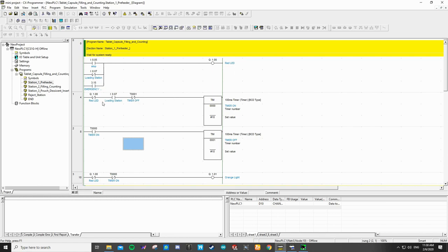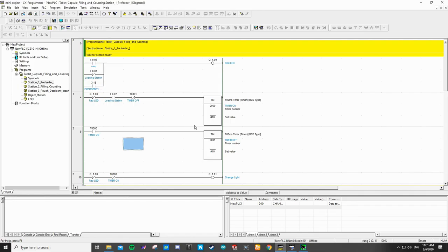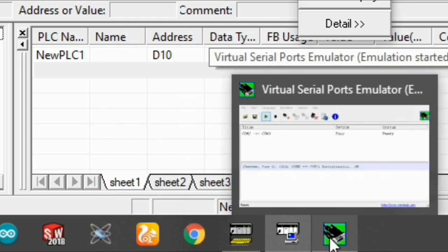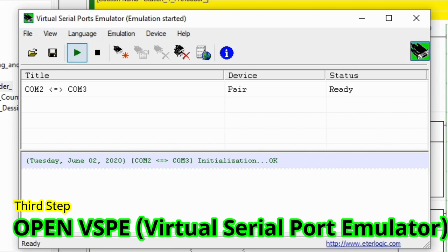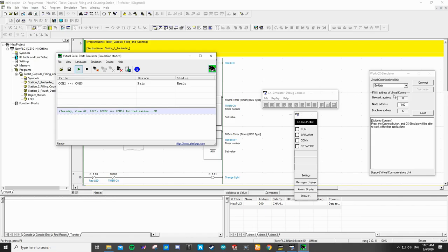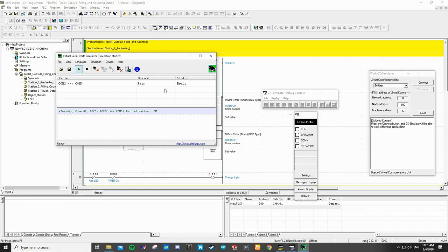First of all, this is an example of my PLC diagram, divided into different sections. Before we connect it to the SCADA, we must open the virtual PLC, which is the CX-Simulator, and then open the virtual port terminal. We use the virtual serial port simulator. As you can see here, this is the pre-setup between COM2 and COM3, which is the pair connection. For the CX-Simulator we use COM2, and for the SCADA we will use COM3 as the communication.